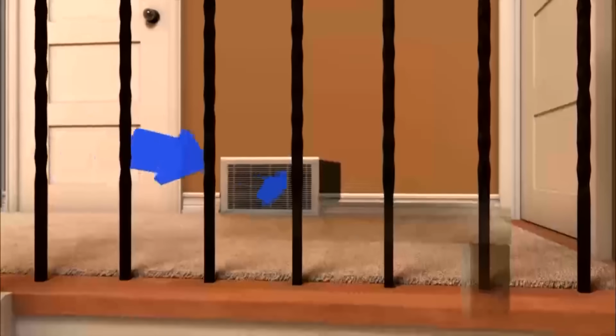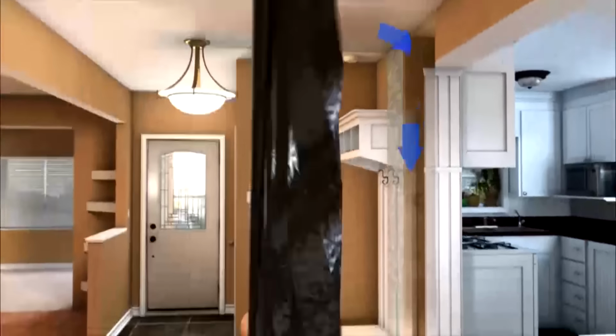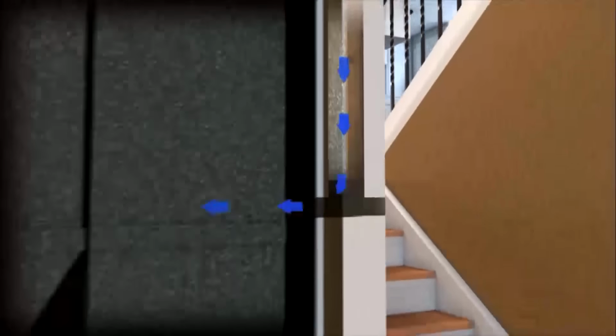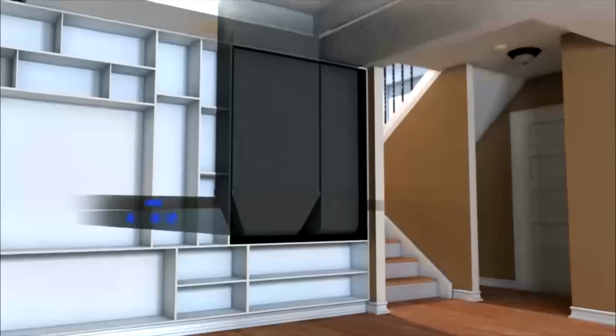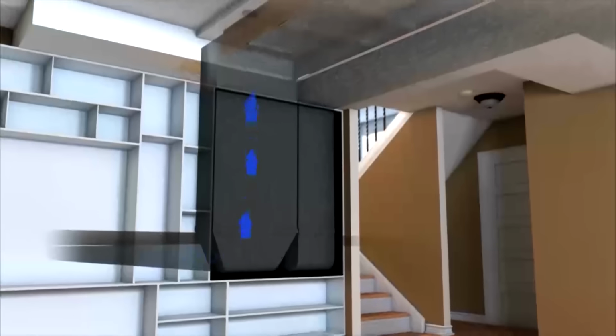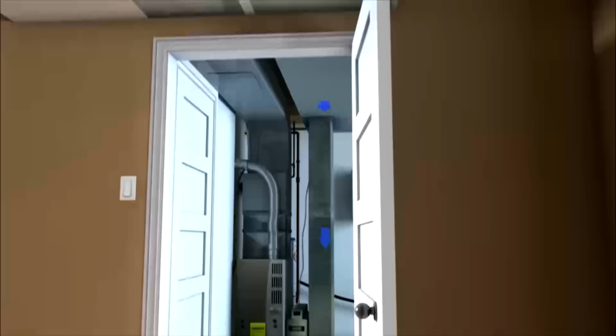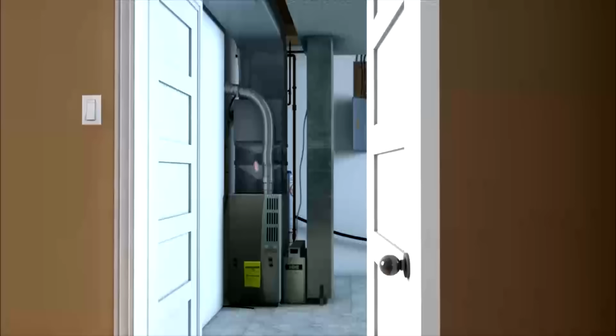With the return being blocked, it's choking off air through the furnace. If the furnace can't draw enough air through the return, it can't supply enough air to the rest of the house. That's causing poor airflow and a lack of heat throughout the whole house. There should be at least one return air per floor, but here we only have one feeding the entire house. No wonder this family's cold.